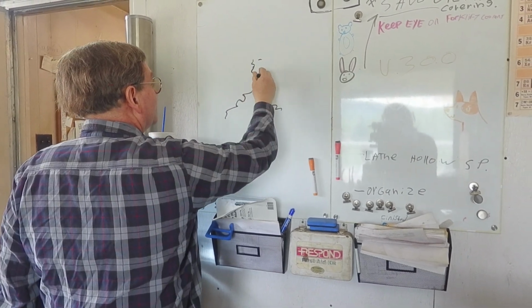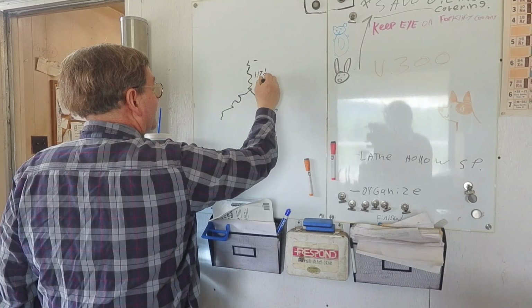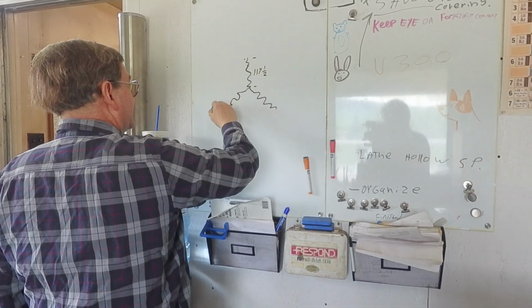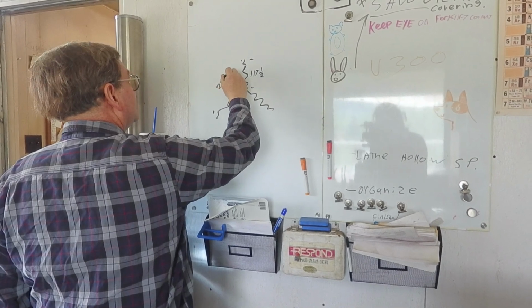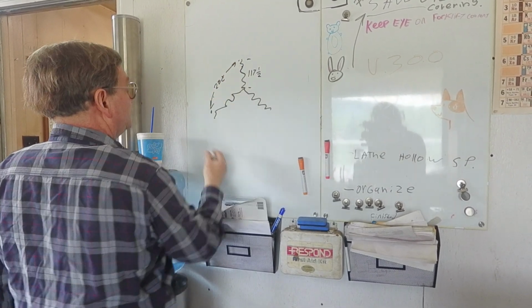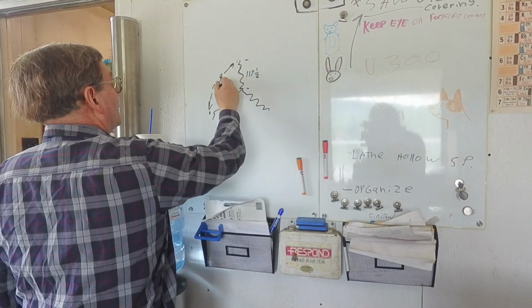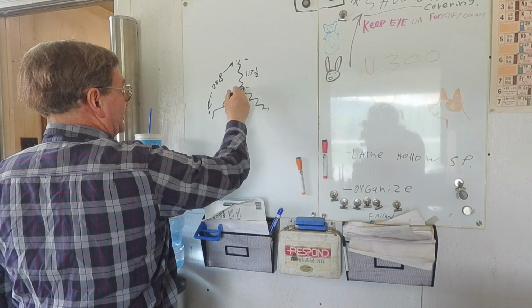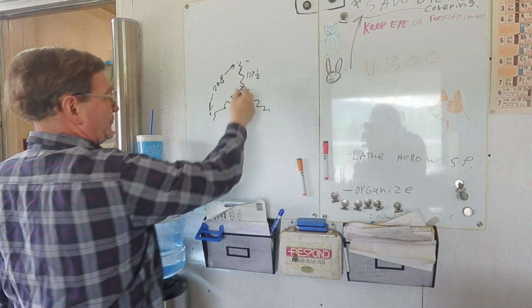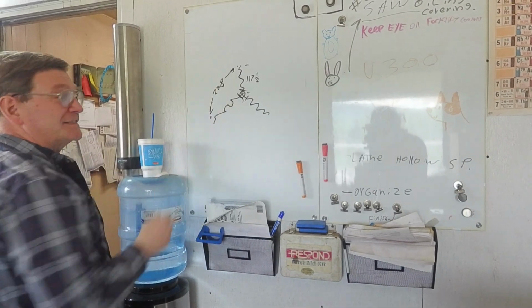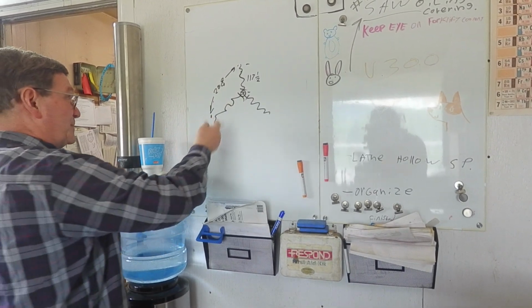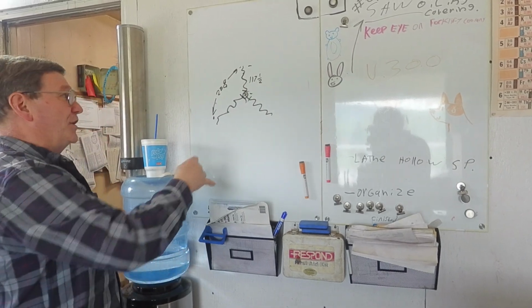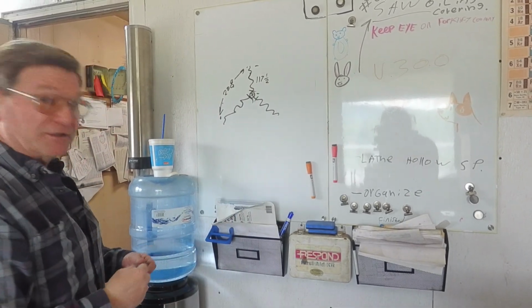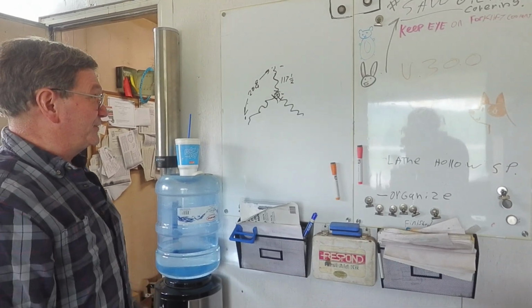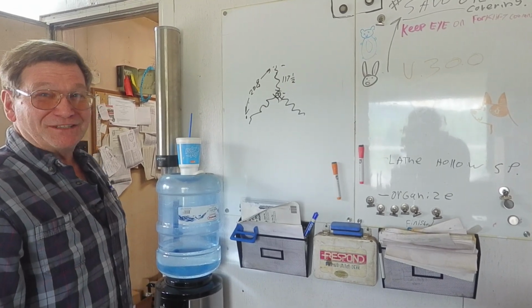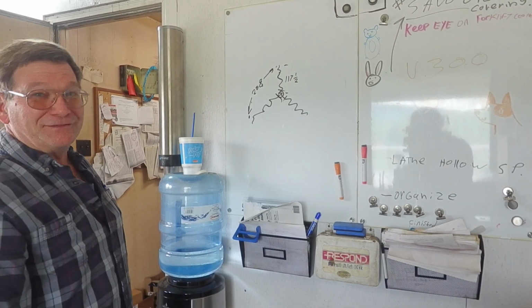So from here to here, you have 117 and a half nominally. And from here to here, you have 208. That's your normal voltage. So by disconnecting this one here, you cut that loose, you now have 3 independent coils that are 117 and a half each. And you can use those as bucking coils or boosting coils onto your 480 that's nominally coming into your shop. And if you don't understand that, I'm not going to go into the whole explanation of bucking and boosting. Talk to one of your electrician friends.